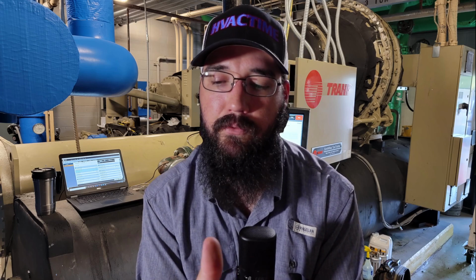If it does reverse, and when it's supposed to be closing, it's actually opening, and vice versa, let's just swap the wires. You just swap the wires where it wires into the harness. That will reverse the polarity, and it will sync everything up. Okay, so it is a very simple fix, but it's something we have to verify upon repair. Otherwise, we're not going to have control of our valve, and we're literally doing the opposite of what we needed to do at the time.